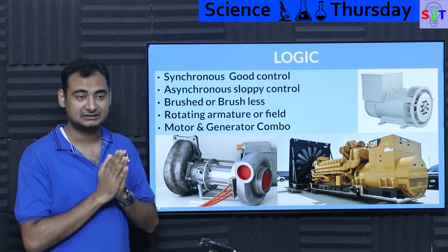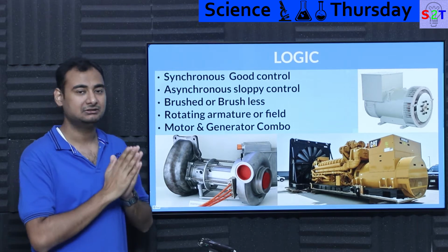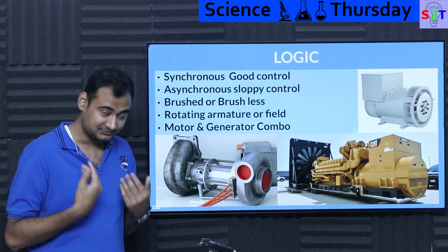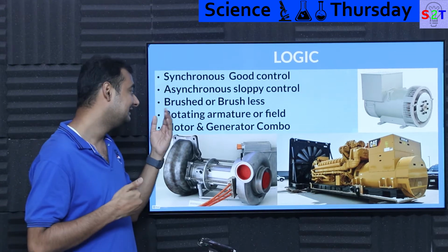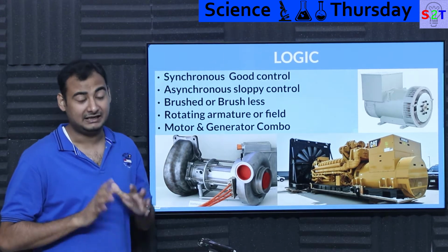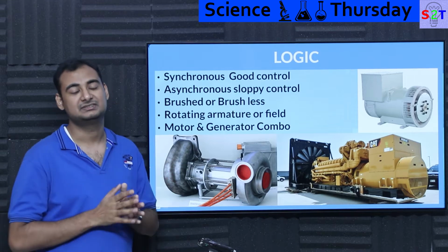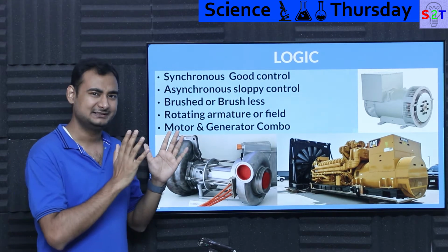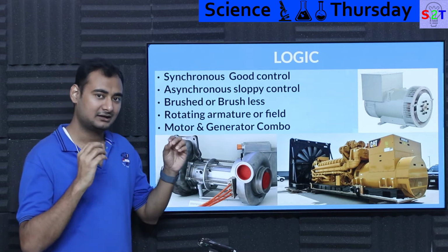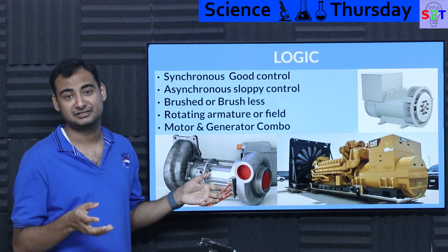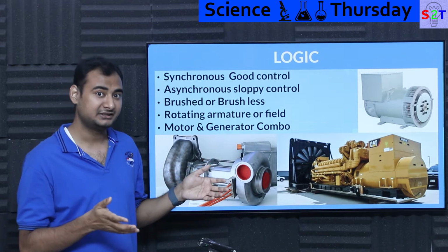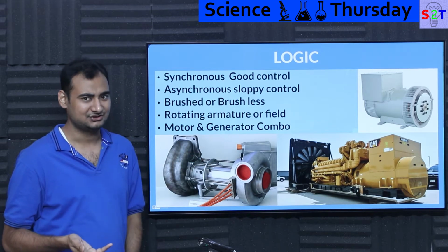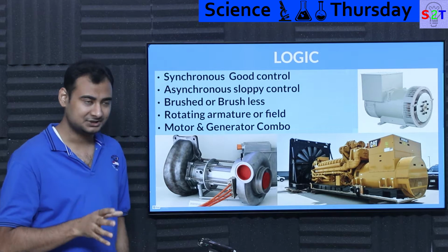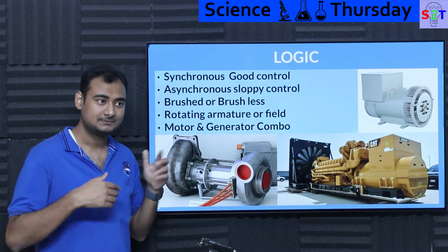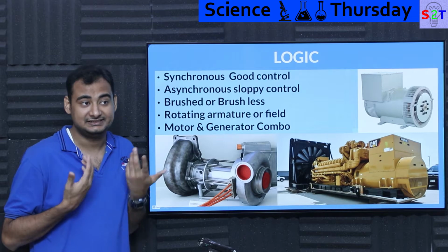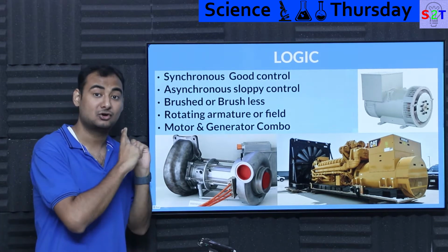Most of the time, the moment you mention rotating armature design, people say rotating field is much better. That's absolutely true, but I never understood why rotating armature design is so prevalent in India. My assumption is that it resembles a motor system way too closely. If a company can manufacture a good 3-phase induction motor, or a slip ring induction motor, that's more or less what you need for a generator. So at low budgets you find rotating armature designs, because despite having hundreds of flaws, it's super easy to mass produce, which is why cost plays such an important role.